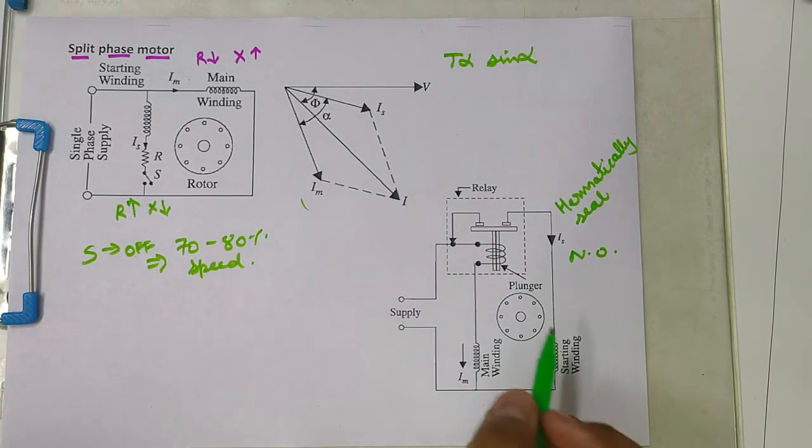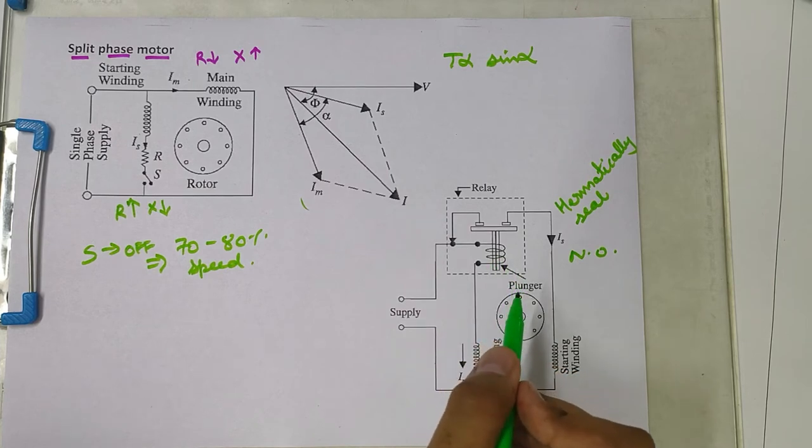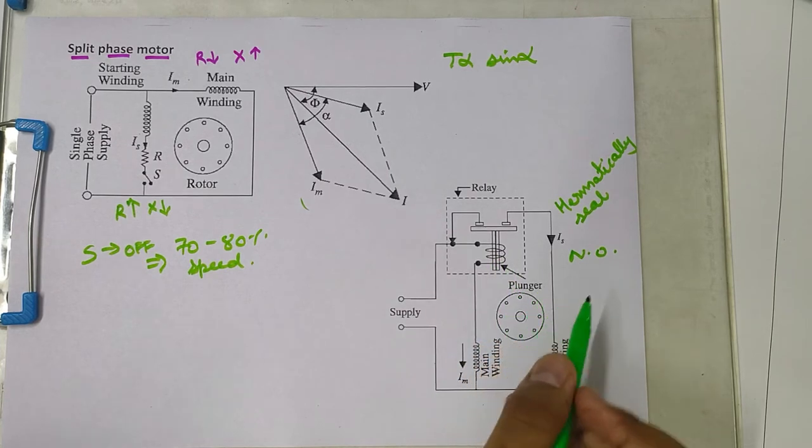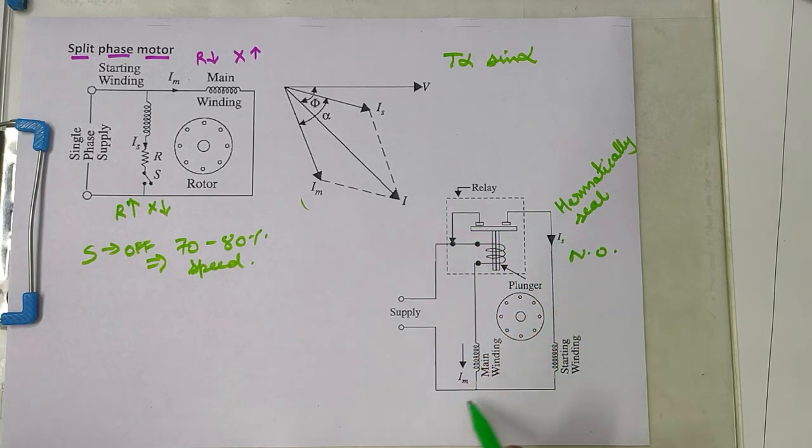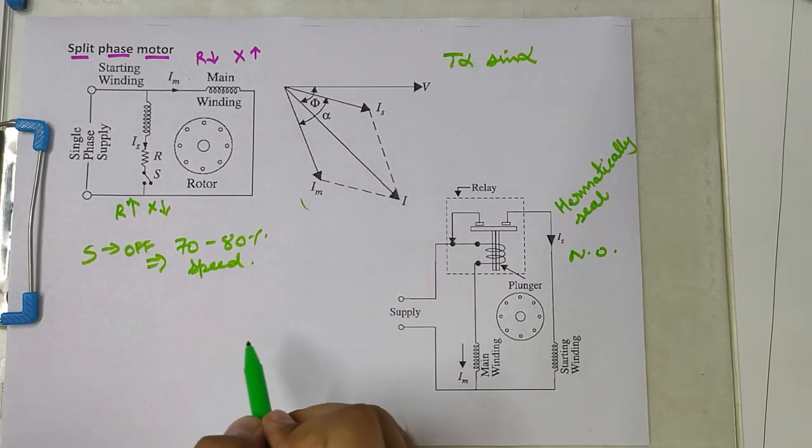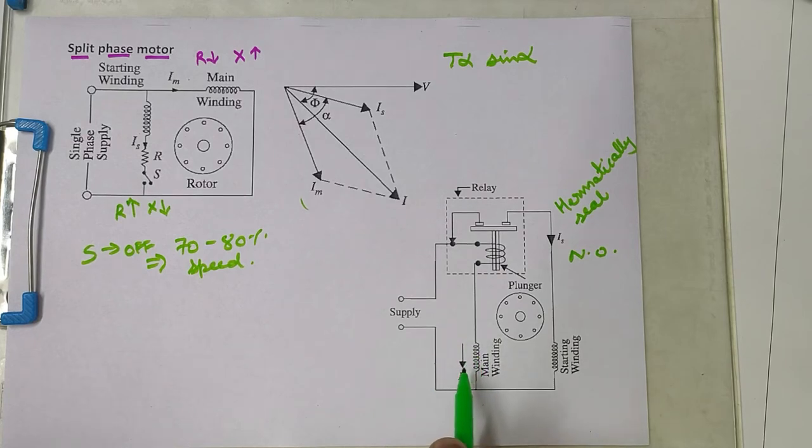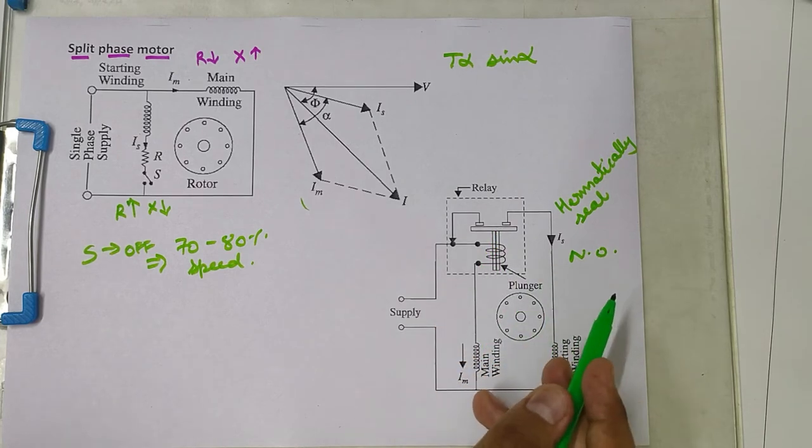During the starting period when the IM, the main winding current, is very large, the relay contacts are closed by the plunger action. This allows IS to flow. As this contact is closed, the starting winding will be connected to the circuit and the motor will start as usual. When the motor reaches 70 to 80% of the speed, IM value will drop and so the current is not enough to keep the contacts closed, and so this will come in normally open position.